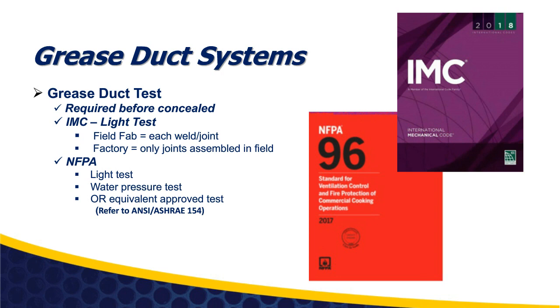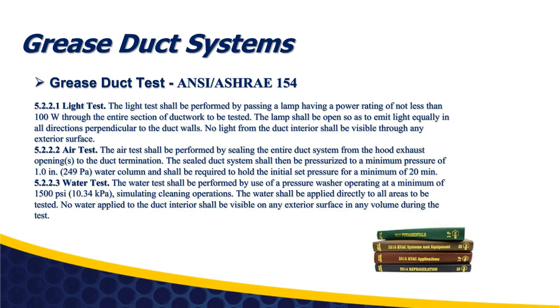NFPA 96 is going to reference a few different tests. One would be a light test, just like the International Mechanical Code. It does make reference to a water pressure test, and then it makes a reference back to ASHRAE standard 154. So if you pull up ASHRAE standard 154, it's basically going to list out 3 separate possible grease duct tests that could be conducted that would be acceptable to the local jurisdiction. One would be the same light test that was addressed in the International Mechanical Code and NFPA. But the second one would be an air pressure test, where basically the system would be sealed and pressurized to a minimum of 1 inch of water column and required to hold that 1 inch of water column for a minimum of 20 minutes to say the duct is acceptable and will not leak.